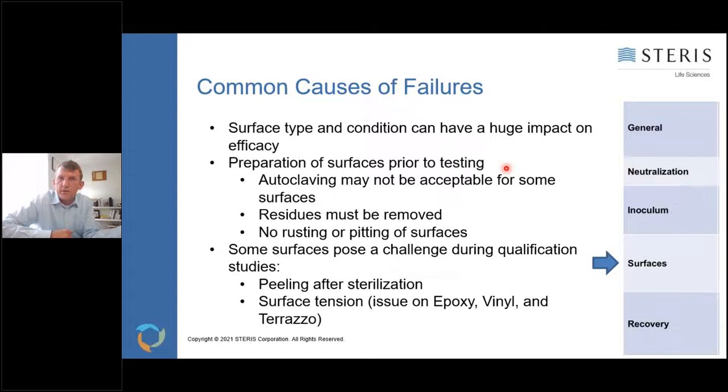You have to make sure that they can be sterilized, so there is no contamination on your surface. And autoclaving may not be acceptable for some surfaces. Some surfaces will not function well after the heat and pressure of an autoclave cycle. You want to make sure there's no residues on that surface that could interact either with your microorganism or with your disinfectant and have some kind of adverse result there. And you want to make sure there's no rusting or pitting.